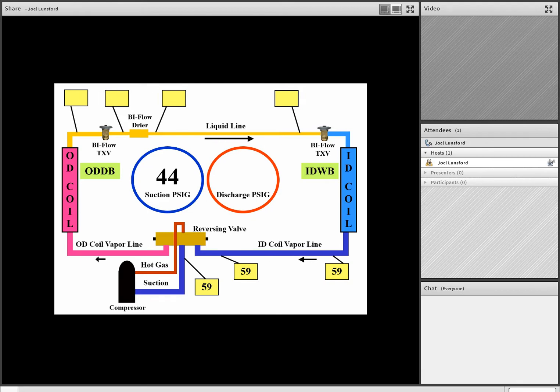So the yellow temperature blocks that are engaged at this time are the ones along the suction line circuit. And we see that it's 59 degrees along the cool suction vapor line with the heat pump in the cooling mode of operation. We also notice it's an R22 call because our gauges have a white background. Now remember, team, if they had a pink or rose-colored background, that would mean it's an R410A call, and we'd use the appropriate chart on our pressure temperature chart. So as we take a look at this example, we see we have 44 pounds of suction pressure, R22.